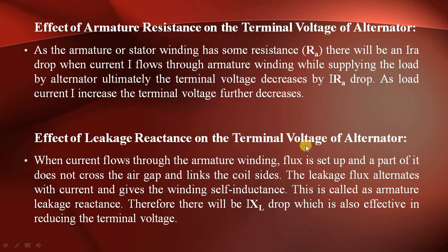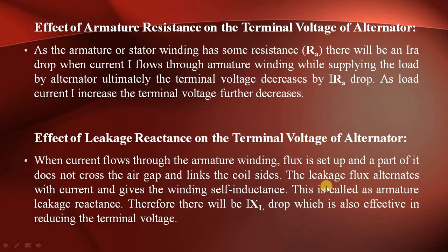Now we will see the effect of leakage reactance on the terminal voltage. When current flows through the armature winding, flux is set up. Part of this flux does not cross the air gap — it links only the coil sides. This leakage flux alternates with the current and gives the winding a self-inductance, called the Armature Leakage Reactance.